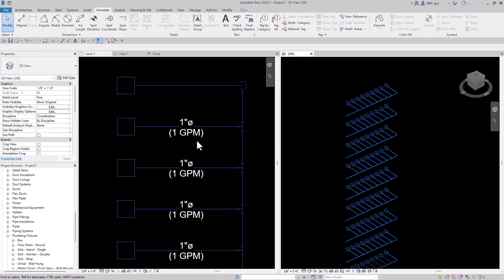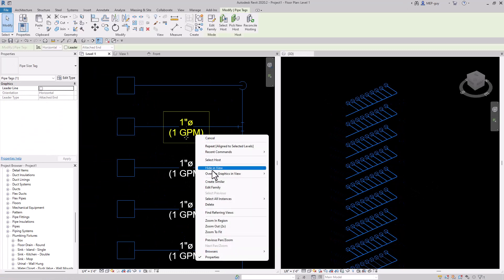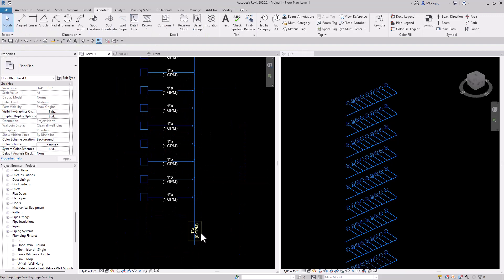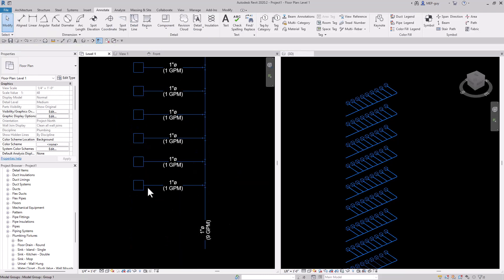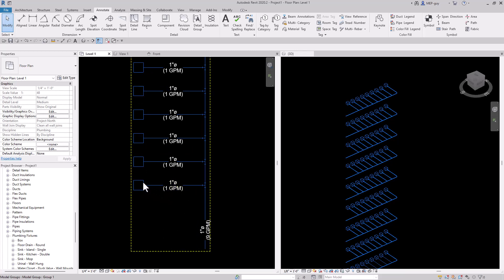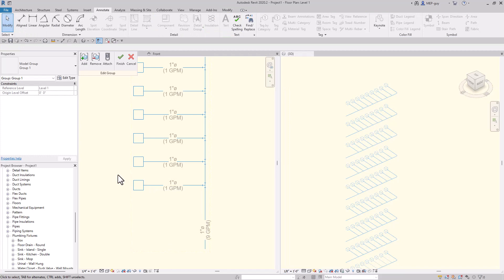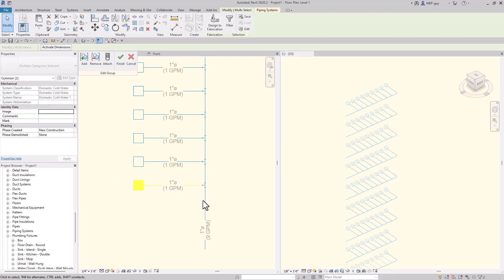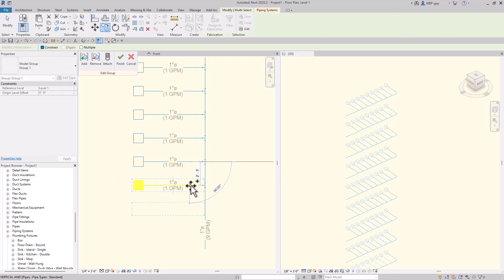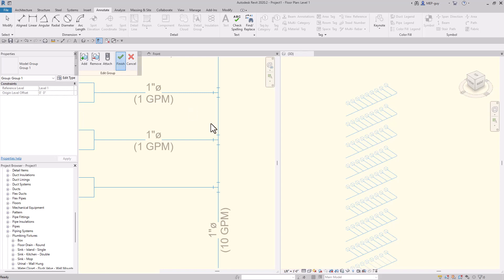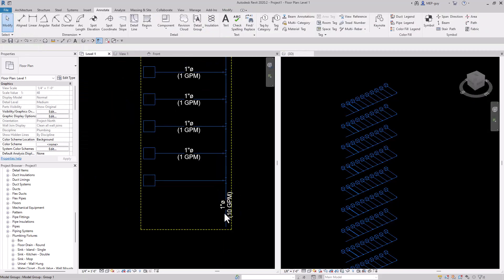I'll right click, create similar, and add that tag back. I can see I have 9 GPM. Maybe we want to re-add that fixture we removed before. Let's double click onto our group, select our fixture and piping, copy it to this location, use the trim command to trim that together, and now we're back to 10 GPM.